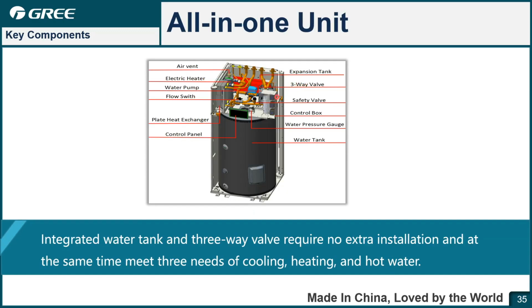Next one is the all-in-one unit. The outside is the same as the split, but for the indoor unit, the hydro box is integrated with the water tank. They are in the same casing. So here is the control panel, PHE, flow switch, water pump, e-heater, this one, air discharge, expansion tank, three-way valve here, safety valve, control box, water pressure gauge, and water tank. So you can see there is also a three-way valve built in.